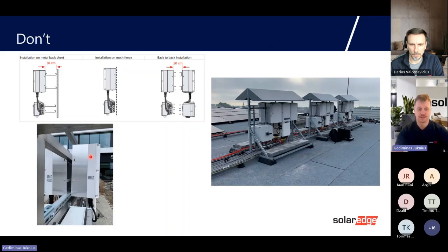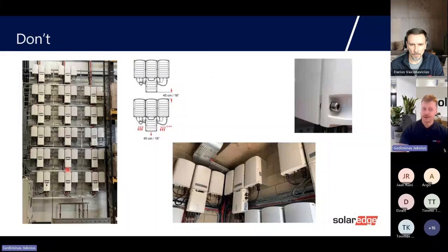And it's obvious that if you have a grill, which is a radiator here, it's not logical that the heat goes from one inverter to the other inverter. I mean, it's not okay. Here again, this is a very famous story and photo from one of the installations we have. And here we see that the gap between the top and the low rows is less than 40 centimeters. And it's not okay. They needed to reinstall the inverters and make bigger gaps.